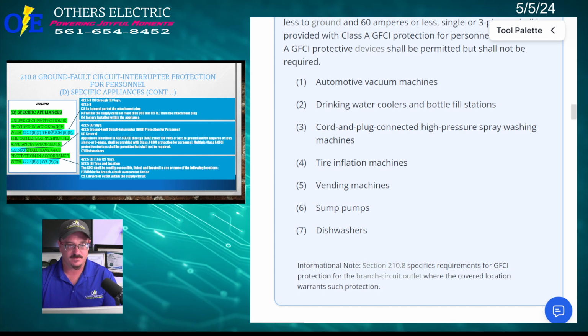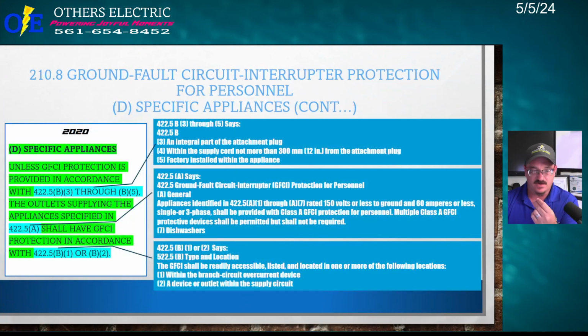Okay. 422.5A. They put that code reference in there. And now it has all these other things. So dishwashers are still required to be GFCI protected. But hey, there's an exception. Because if you have a dishwasher that has an integral GFI as an integral part of the attachment plug, or, let me go back into this one right here, within the supply cord not more than 12 inches from the attachment plug, or factory installed in the appliance, you don't have to be GFI. I've never seen one, so.